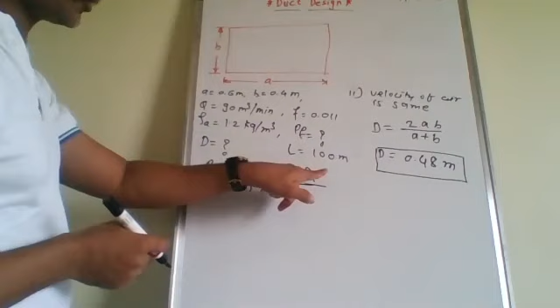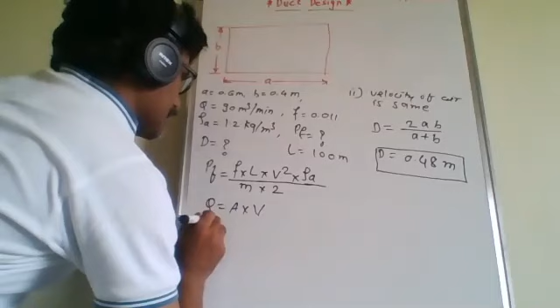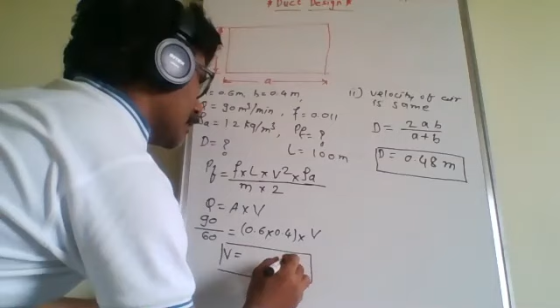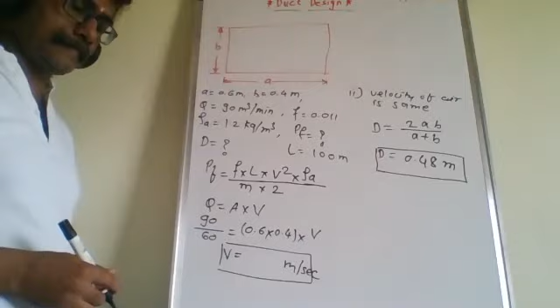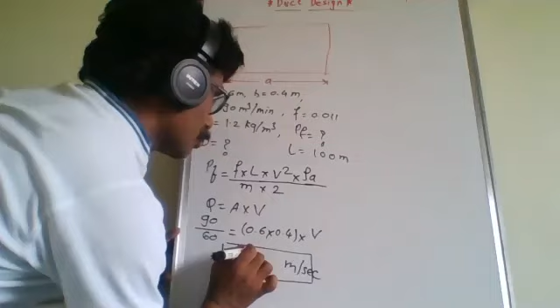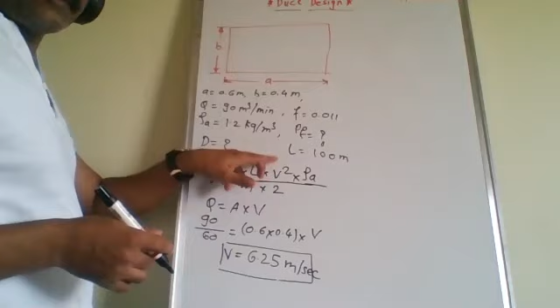So F is given to us, L is given to us, rho A is given to us. We have to find out the V. So Q equals area into velocity. The discharge is given as 90 meter cube per minute. So 90 divided by 60 to get that in meter cube per second, and it is a rectangular duct, so area 0.6 into 0.4 into velocity V, in meter per second. Velocity is 6.25 meter per second. So velocity is determined. We have to find out this M, hydraulic mean radius.